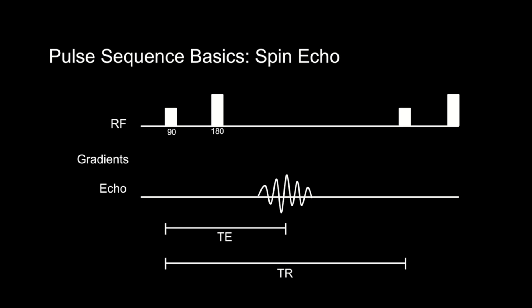In a spin echo pulse sequence, there are two RF pulses at the beginning: a 90-degree RF pulse followed by a 180-degree RF pulse. Technically a spin echo can start with any two RF pulses, but most commonly we use a 90 followed by 180 degrees — that's how we identify it as a spin echo sequence. The 90-degree RF pulse tips the spins into the transverse plane and causes the nuclei to precess in sync in the XY plane.